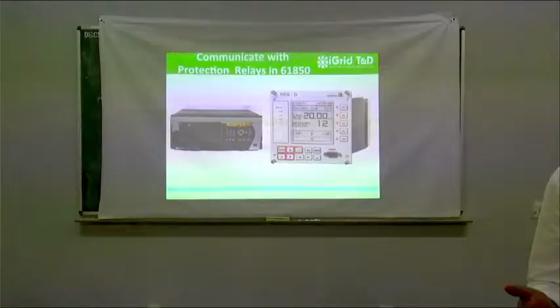And one more major component is the GPS. When I give a SAS panel, this typical SAS panel will contain Ethernet switches and the gateways, and sometimes we also fit our SCADA screens or the SAS systems into the SAS automation panel itself. Here, GPS is used for time synchronization for all the relays. So when we are doing time synchronization, we are using the SNTP protocol for synchronizing the time with all the relays.